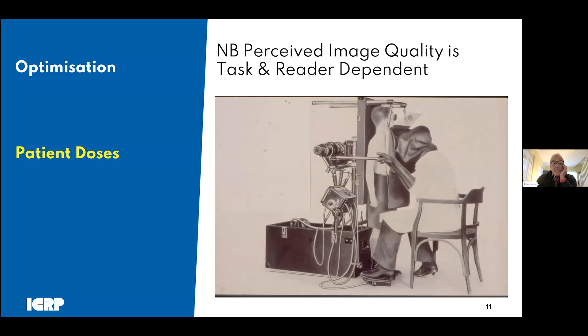A core principle is that patient dose should be adjusted to the minimum level required to provide an adequate image. So it's important not to lose sight of the fact, as Colin's already said, that the dose we want is a dose required to achieve a desired image quality, and that image quality is both task and reader dependent. That is, the choice of factors that influence both patient dose and image quality depend on the patient, the clinical question, the examination, the operator performing the procedure, the equipment used to image the patient, and of course the person interpreting the eventual image.